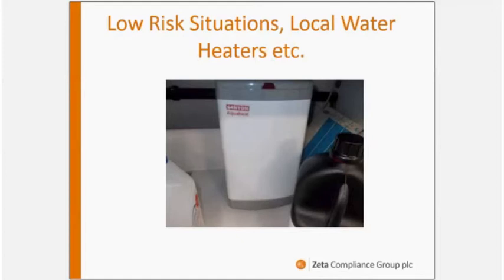It's recognizing that common sense idea we've always had, that a little thing not much bigger than a kettle under the sink isn't putting life and limb at serious risk. It could grow Legionella if it's warm, but intuitively you can see that it is a very, very different proposition to a large system that's not working properly, which has got warm, stale water in it coming out of a shower. This is a very, very different thing, and this is now recognized. It's given us a bit more work to do in one area, and possibly a little bit less in another.